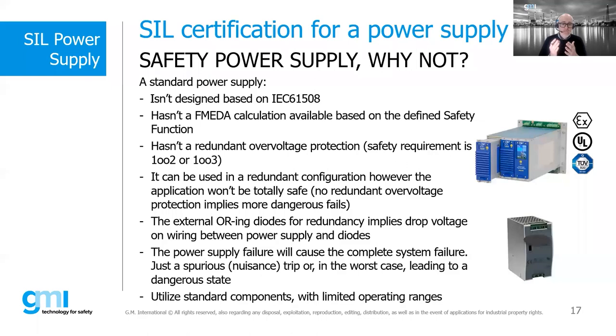And again, standard power supplies use internal components with limited operating range to keep costs down. This affects the lifetime of the device. For this reason, internally to the safety power supply, components with a higher operating range are used, which allow the system to work at a lower stress level. This leads to fewer failures and consequently a considerably longer lifetime than a standard power supply system.